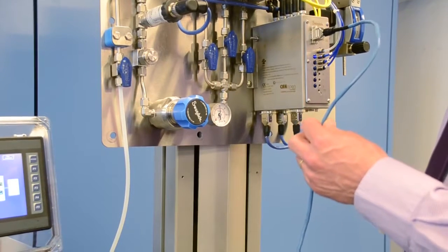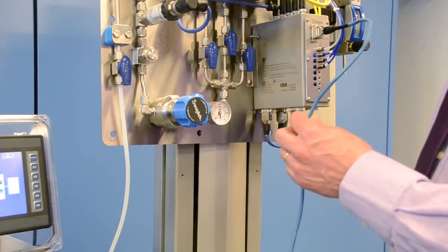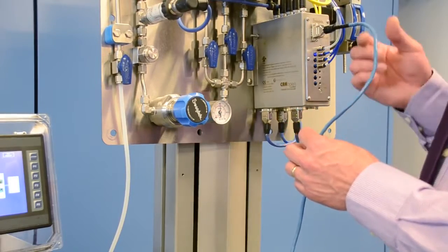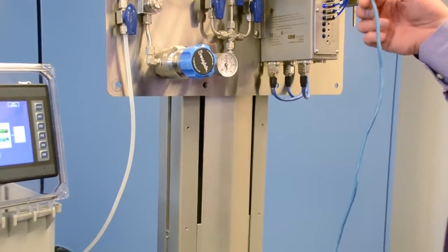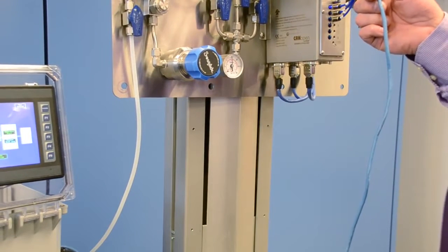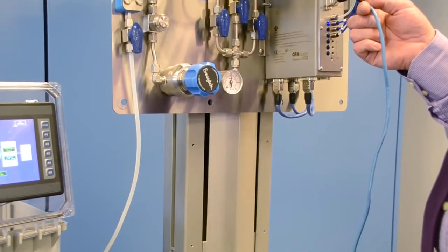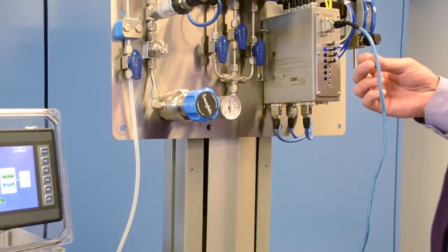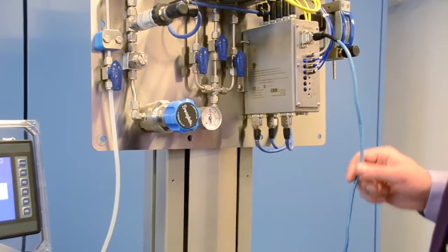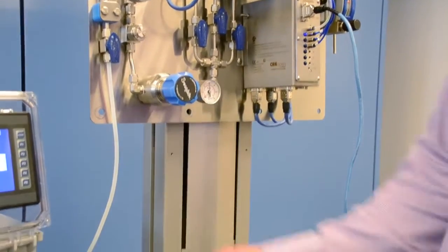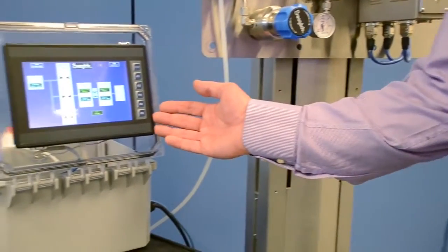Both power and communication are present inside this wire, and this intrinsically safe digital data makes its way through this cable, and the network that is used by the ICM is an open standard CANopen interface. That data makes its way down this cable and ultimately over to our operator control station.